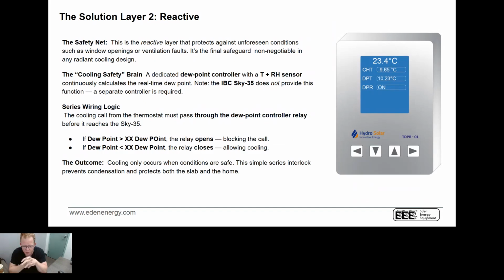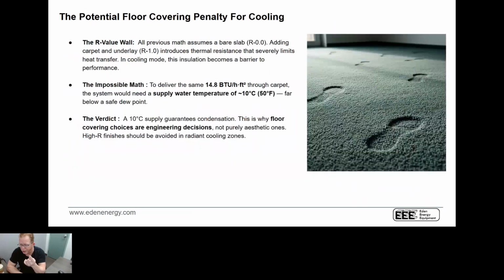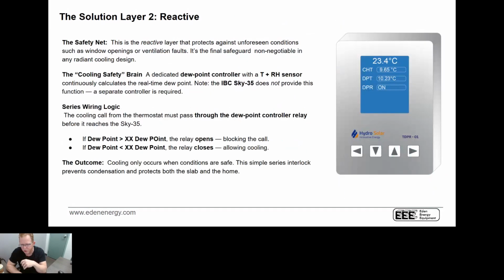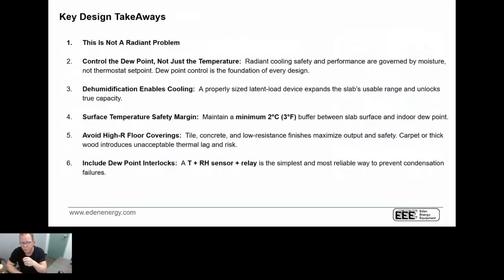You would much rather get a call from a consumer to say, hey, my air conditioning isn't working. You go, yeah. Have you got all the windows open? It's 30 degrees out and it's really humid. Oh, yes, I do. It becomes an education point. The alternative is they call you and say, why is my carpet wet? And you go, well, we did put in a dehumidifier, but we didn't put a dew point controller in, so we may or may not have moisture forming on the slab. Give it a couple of days, it'll dry out. Nobody wants to have that conversation. So it is a two-pronged approach, right?